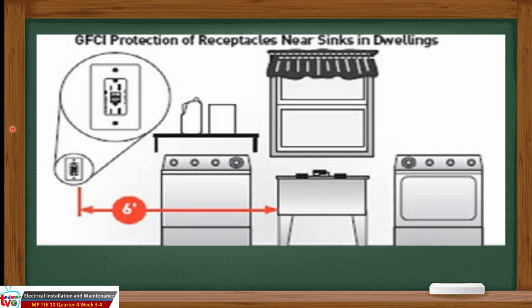The revision is made to emphasize the requirement that all 15 and 20 ampere, 125 volt receptacles within 6 feet of dwelling unit laundry or utility sinks have to be GFCI protected. This is because irons, hair dryers, and similar items with ungrounded, polarized and non-polarized cord caps are commonly used in this area. The same shock hazard is present as in other areas where the national code currently requires GFCI protection.